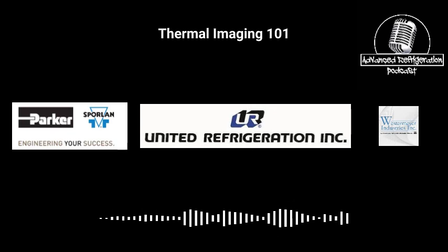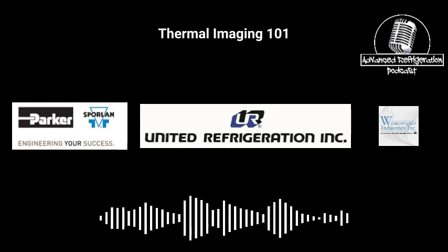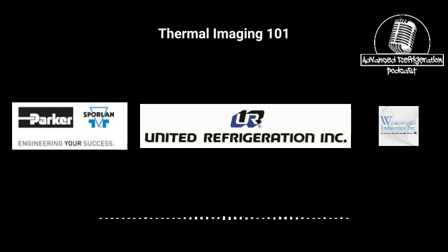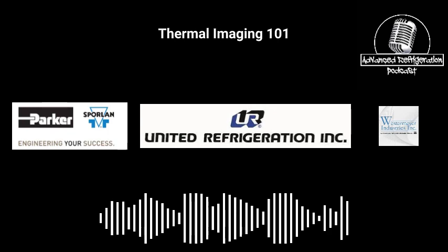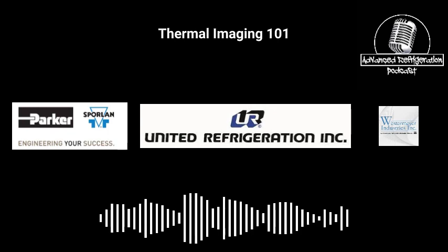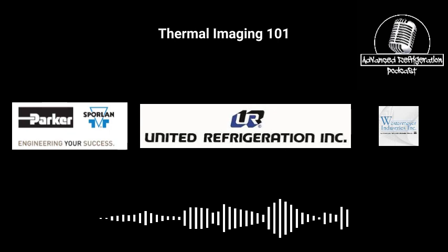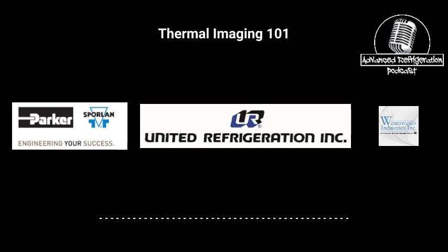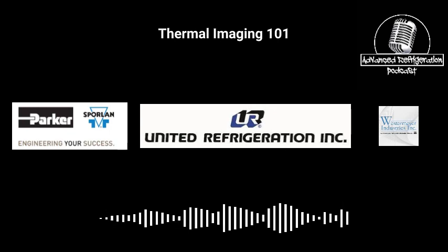You can see this is more like predictive maintenance in a sense. You could tell something's going to fail before it does, because you're able to look at the thermal imager and see the hot spots, and you're able to change that part out or tighten that connection or fix that wire that's burning up before another tech is going to be able to see that. You're able to predict that failure.